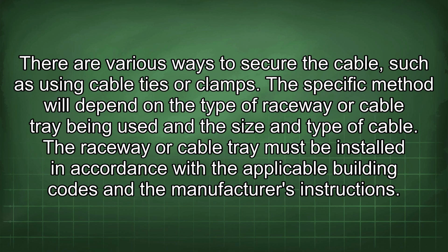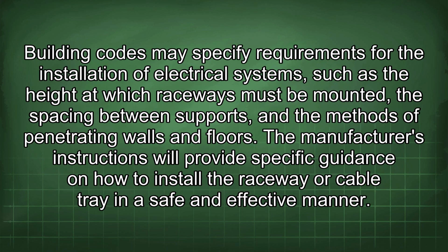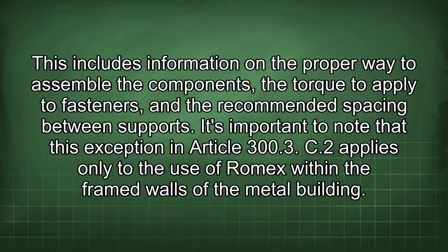There are various ways to secure the cable, such as using cable ties or clamps. The specific method will depend on the type of raceway or cable tray being used and the size and type of cable. The raceway or cable tray must be installed in accordance with the applicable building codes and the manufacturer's instructions. Building codes may specify requirements for the installation of electrical systems, such as the height at which raceways must be mounted, the spacing between supports, and the methods of penetrating walls and floors. The manufacturer's instructions will provide specific guidance on how to install a raceway or cable tray in a safe and effective manner. This includes information on the proper way to assemble the components, the torque to apply to fasteners, and the recommended spacing between supports.